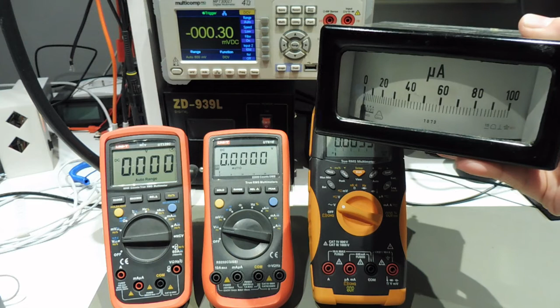These meters here are way more precise. This multimeter has a base accuracy of 0.1% for its voltage range. Usually voltages are the most accurate ranges, because a meter basically just measures voltage internally, and any other unit you measure, like current or resistance, gets converted internally to voltage. So with 0.1% accuracy, when you measure 1 volt, it might be off by 1 millivolt—that's not too much.